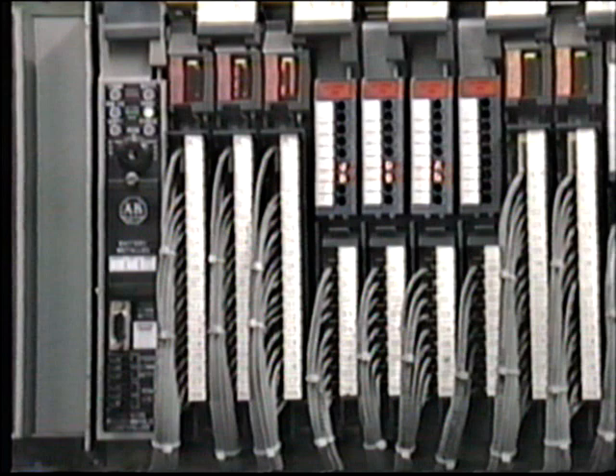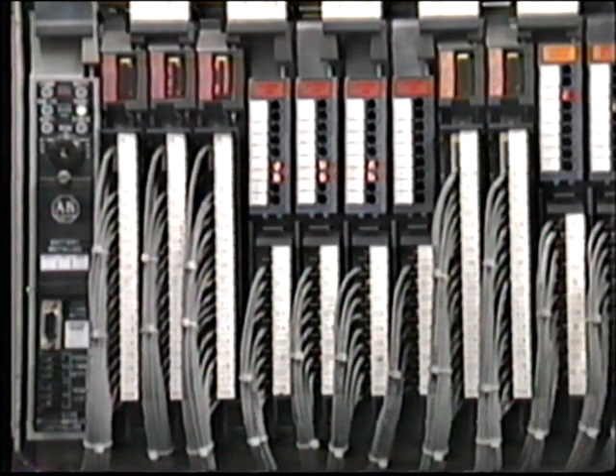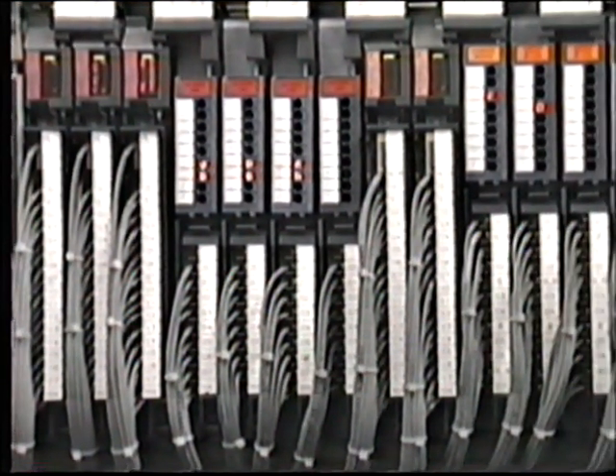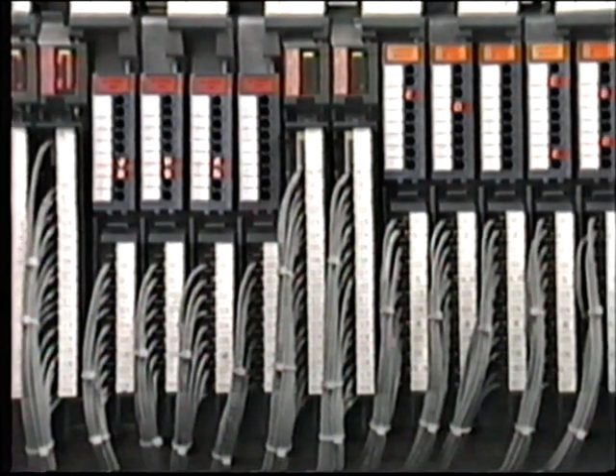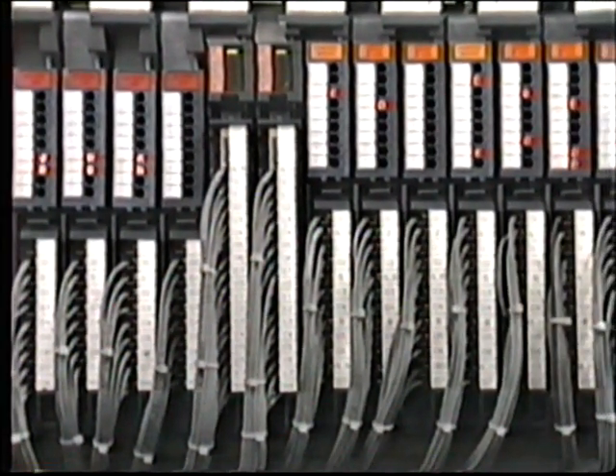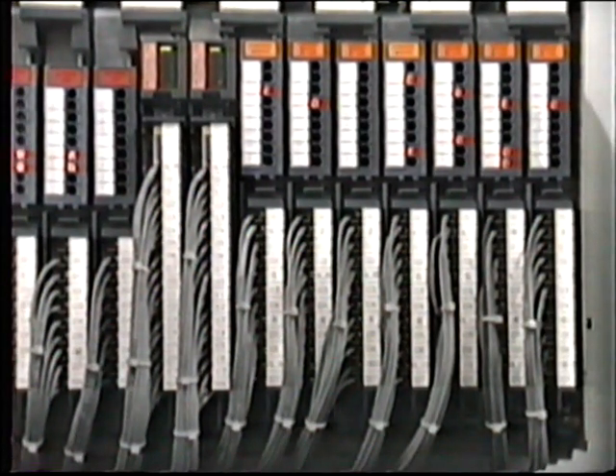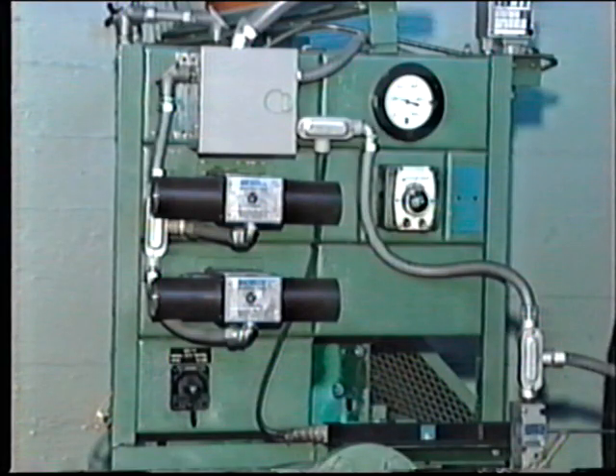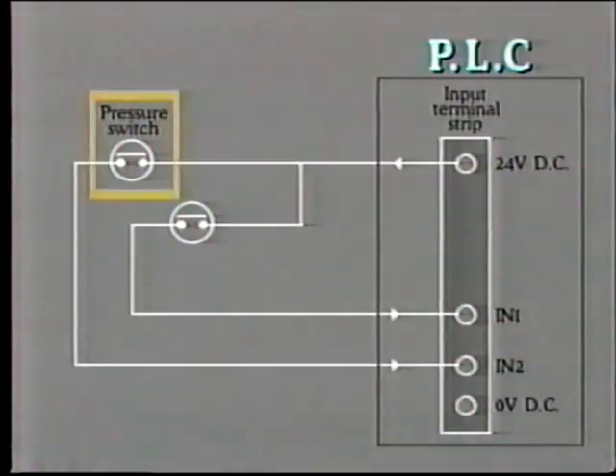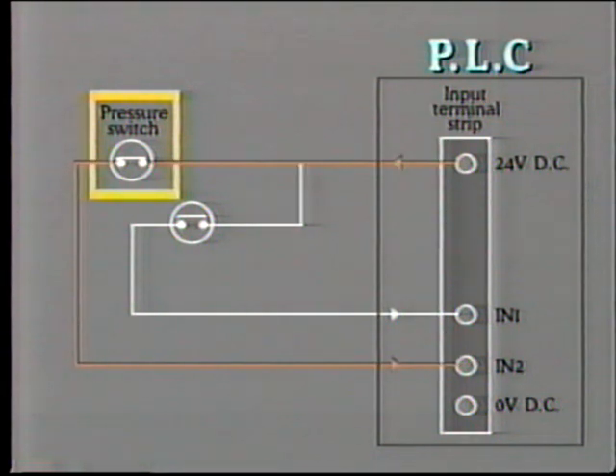In this segment, we're going to look at typical PLC arrangements for handling input and output signals. In most installations, hardwiring is used to connect the sensors in the field to the input terminals at the PLC. Most of the signals are of the on-off type, known as discrete signals. Devices such as pressure switches, temperature switches, and limit switches all provide an on signal when their preset conditions are met. Closing the contact completes a circuit and applies a voltage to the PLC input terminal.